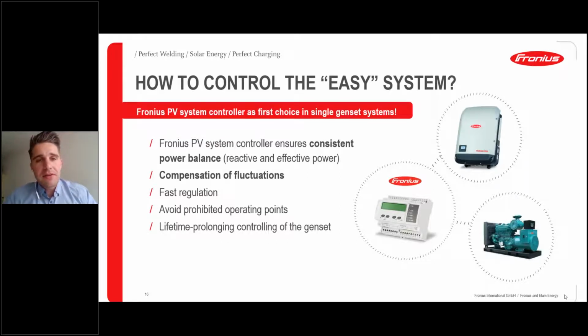So, if you only have 1 single genset, the Fronius PV system controller, which you can see here, is therefore the first choice, of course. What can we do? We can ensure a consistent power balance. That means we all the time watch the load situation. We all the time watch the genset production, and therefore regulate also the PV system. It's a very fast regulation, which is of course necessary to avoid any prohibited operating points, and in order to guarantee stable operation mode and to extend, of course, the lifetime of the diesel genset.